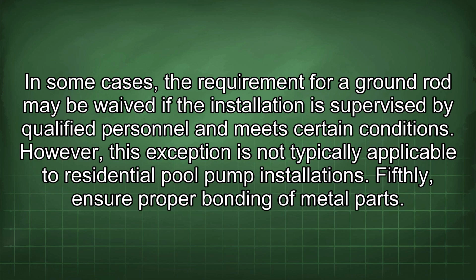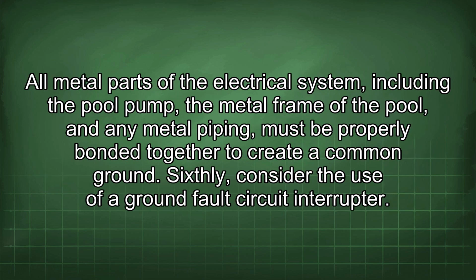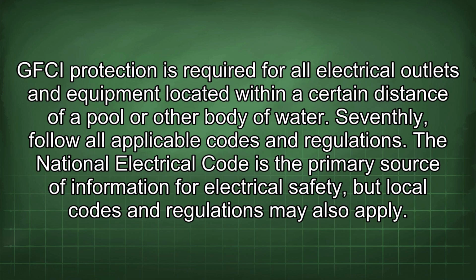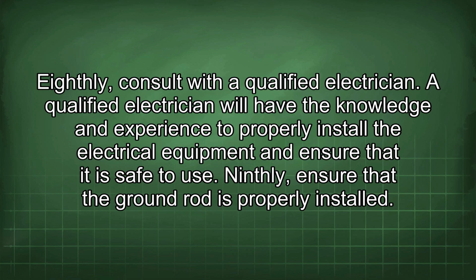Fifthly, ensure proper bonding of metal parts. All metal parts of the electrical system, including the pool pump, the metal frame of the pool, and any metal piping, must be properly bonded together to create a common ground. Sixthly, consider the use of a ground fault circuit interrupter. GFCI protection is required for all electrical outlets and equipment located within a certain distance of a pool or other body of water. Seventhly, follow all applicable codes and regulations. The National Electrical Code is the primary source of information for electrical safety, but local codes and regulations may also apply. Eighthly, consult with a qualified electrician.